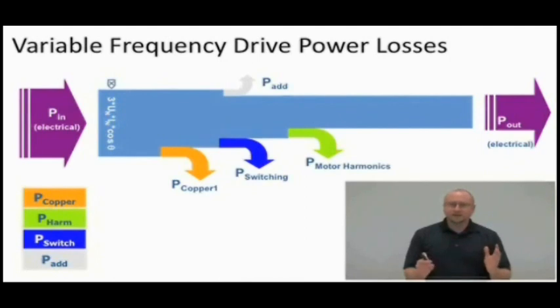If you take an existing system and you don't change anything else, all you do is add a component to it, it doesn't matter what component you add, there's going to be an inefficiency that you're adding to the system, and that gets multiplied for your entire system, and you're going to be losing energy. A VFD doesn't magically operate without any power loss. Of course, there are power losses inside of a VFD. They get hot when they run, so you know that some of that energy is being transferred to heat and not being used. But you do stand to make other gains when you add a VFD.